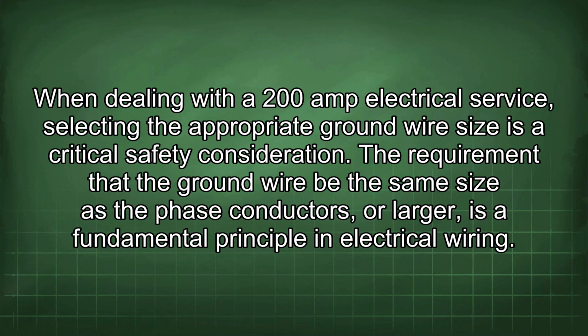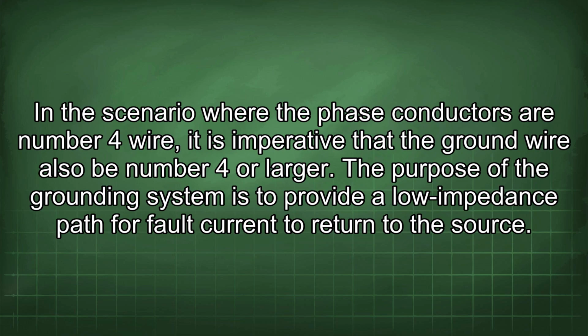When dealing with a 200 amp electrical service, selecting the appropriate ground wire size is a critical safety consideration. The requirement that the ground wire be the same size as the phase conductors, or larger, is a fundamental principle in electrical wiring. In the scenario where the phase conductors are number 4 wire, it is imperative that the ground wire also be number 4 or larger.